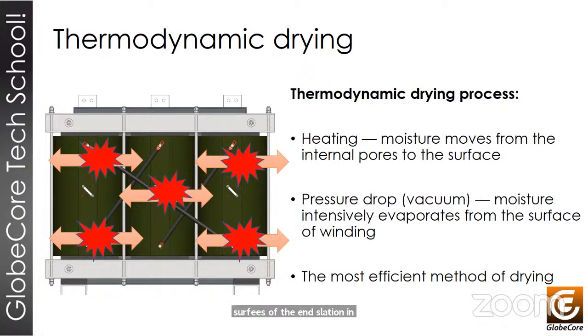In order to speed up drying, the maximum allowable temperature of 100 to 110 degrees Celsius for paper fiber insulation and vacuuming are applied. Vacuum serves to reduce the vapor formation temperature, to speed up drying, and to remove water vapor from the drying unit, as well as to maintain the relative humidity of air inside this unit at a low level. The thermodynamic drying process resides in the fact that the insulation heats up and moisture moves from its internal pores to the surface, and then to the environment.